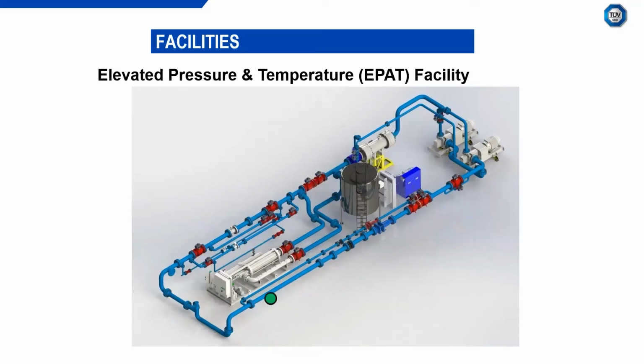It's just a way to demonstrate it. So it's flowing around through the system. That's where the test meter would be installed, back through the pump and around again. So you can see it flowing around through the heat exchanger, down through the prover, through the reference system, and then flows up. That's the test section there. That's typically where we would install the device under test, be it a Coriolis, an ultrasonic, turbine, or differential pressure device.